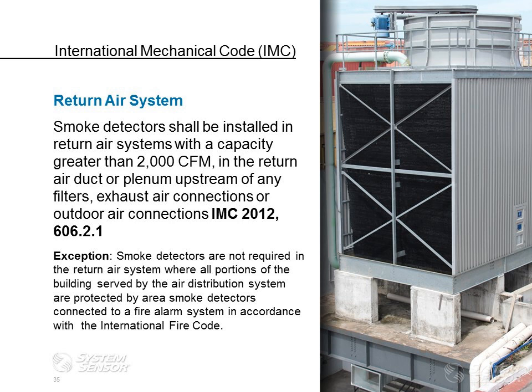Some people read that, and again, this is interpretation, but what the code is actually stating is that if you have a total coverage system, then you're not required to have duct detectors. But anything short of a total coverage system, which would be a partial coverage system, does require duct smoke detectors. Now, the International Mechanical Code says that if it's greater than 2,000 CFM or 5 ton or larger, it has to have a duct smoke detector in the return side.